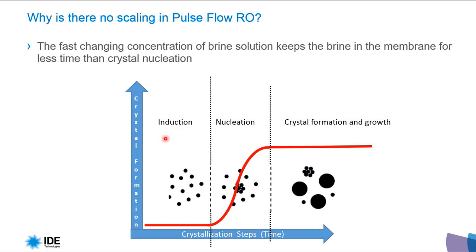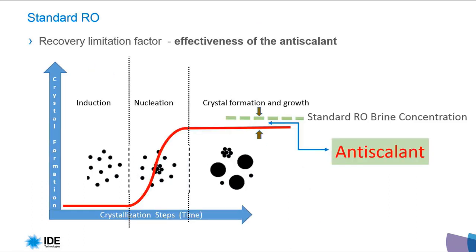The scaling process consists of three stages: induction time, nucleation time, and crystal formation time. Induction time is when solute ions inside the solvent organize themselves in a way that enables nucleation — forming protocrystals. Later, from the protocrystals, a crystal grows. The process of crystal formation can continue for a very long time, while the induction time is relatively short.